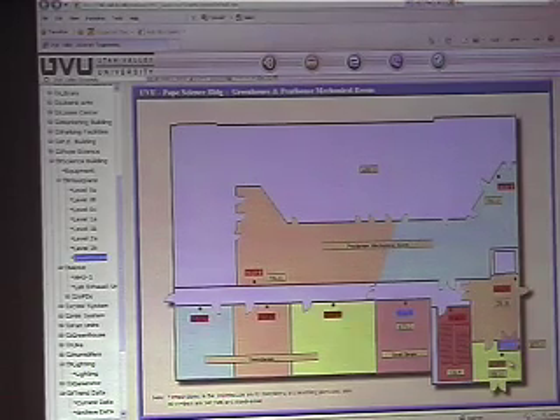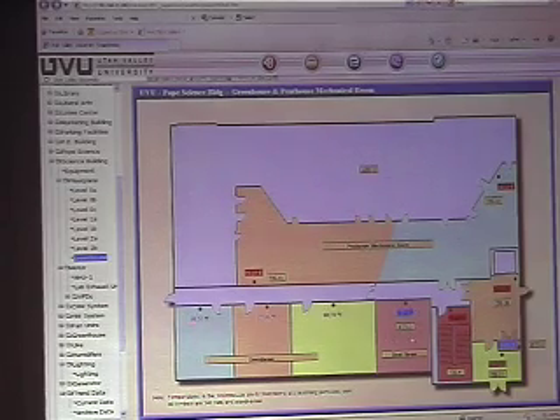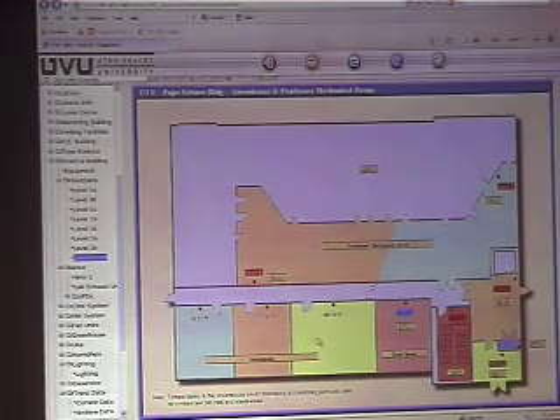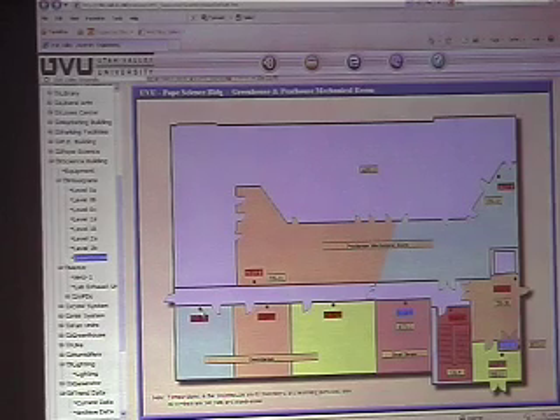Unit heater in this storage area, and then there's a unit heater in the stairwell. There's a rooftop unit that serves this head house section of the greenhouse. The greenhouse section itself is all standalone equipment. All we're doing here is monitoring temperatures in these areas. They called for us to show an alarm on these temperatures if the space temp gets below, I think it was below 70 degrees in there.